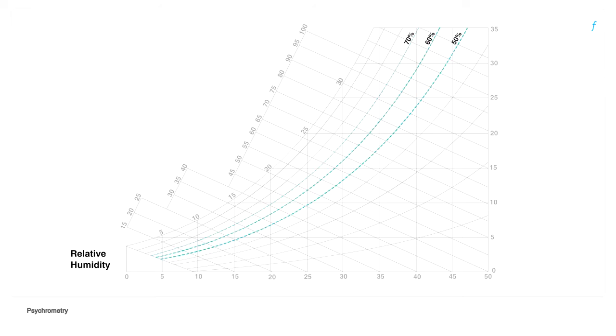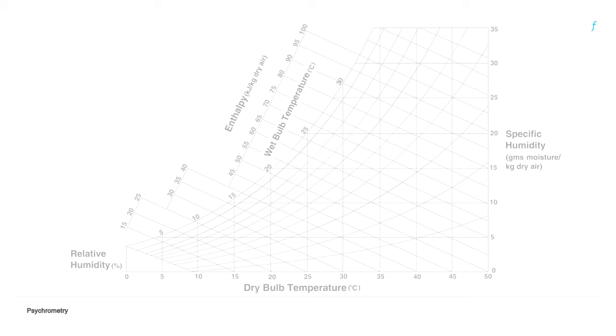Moving towards the right or left on the chart parallel to the x-axis would be sensible heating or sensible cooling where the dry bulb temperature changes without a change in the moisture content of air. Moving parallel to the y-axis would cause humidification or dehumidification, changes in humidity levels of air without changing the dry bulb temperature.